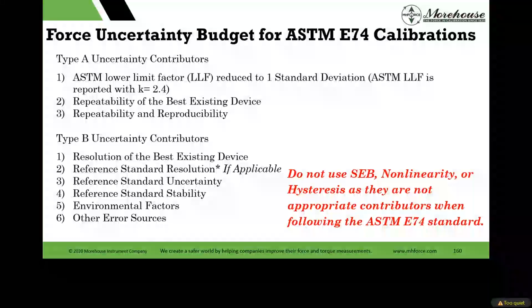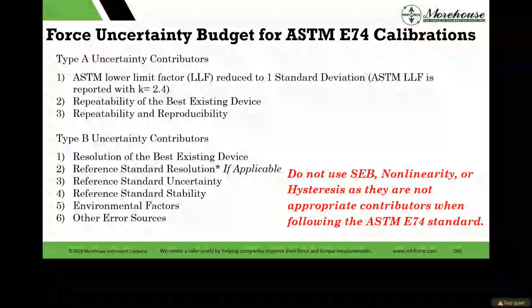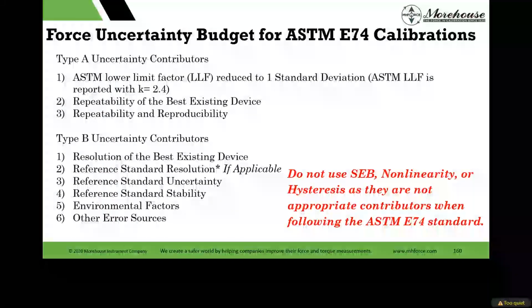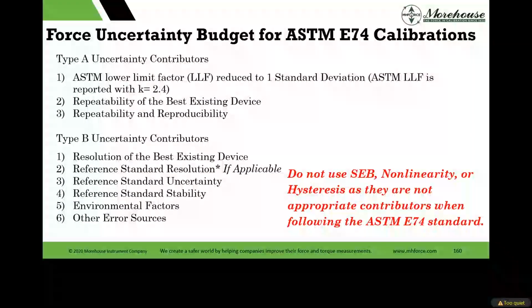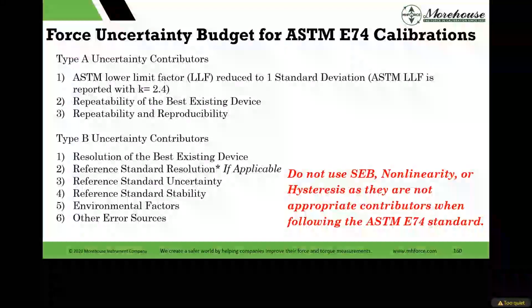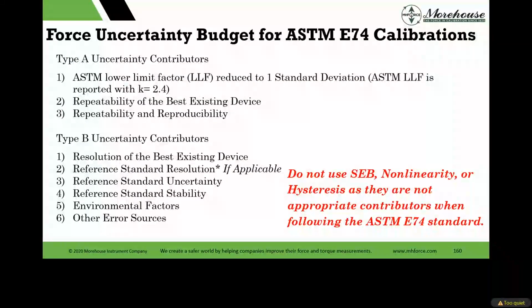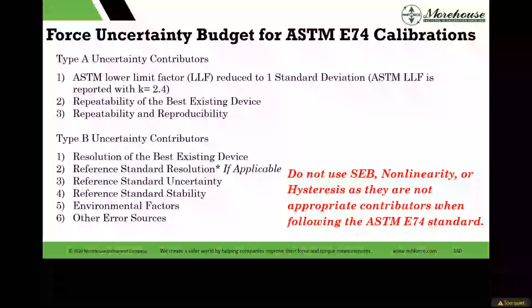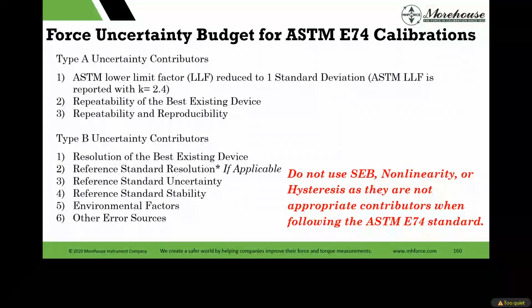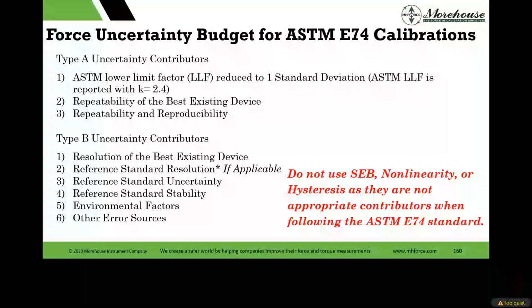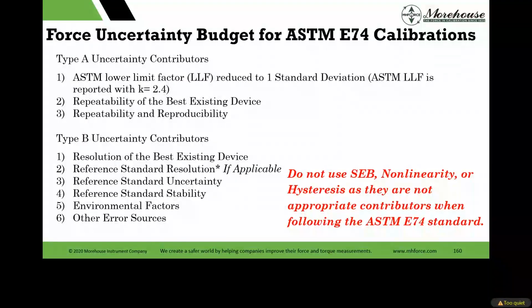If you use E74 and you're familiar with JCGM, the Guide to the Expression of Uncertainty in Measurement, people call it the GUM, it starts talking about Type A, Type B. This is not a full uncertainty class. So you have that reproducibility component quantified. Your calibration is done in accordance with a legal documented standard, which is your CYA, or CYB is a better term, cover your butt. I've sent it off, even though I'm not calibrating equipment to class A, double A, whatever, and I have an E74 calibration. That makes my life so much easier, because I have this documented legal standard.